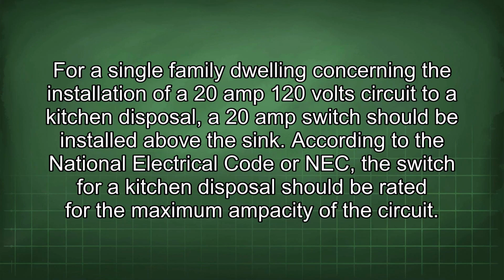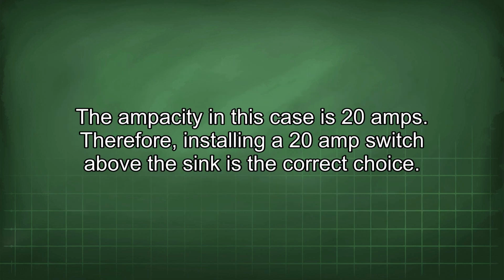For a single-family dwelling concerning the installation of a 20-amp 120-volt circuit to a kitchen disposal, a 20-amp switch should be installed above the sink. According to the National Electrical Code or NEC, the switch for a kitchen disposal should be rated for the maximum ampacity of the circuit. The ampacity in this case is 20 amps. Therefore, installing a 20-amp switch above the sink is the correct choice.